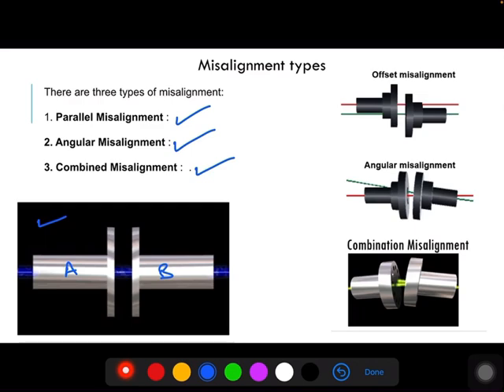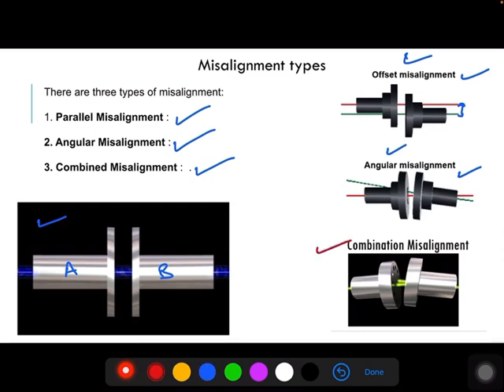What is parallel misalignment? When the axes of the shafts are parallel to each other and not intersecting, but there is an offset between the two axes, it is called offset misalignment. If the two axes are not parallel but they are intersecting, then it is called angular misalignment. In general, for any equipment, there will be a combination of both offset and angular misalignment — this is called combined misalignment, and we generally see this in any rotating component.